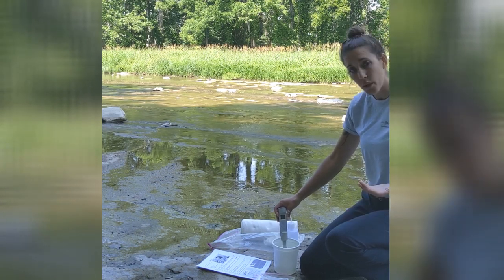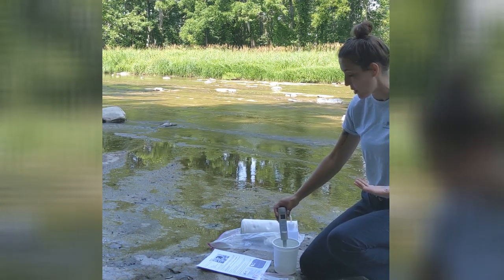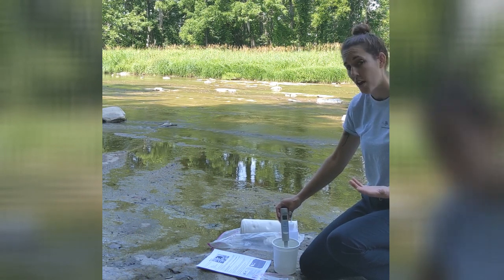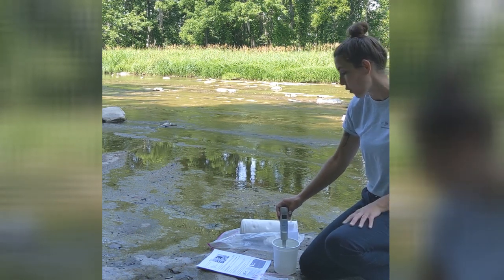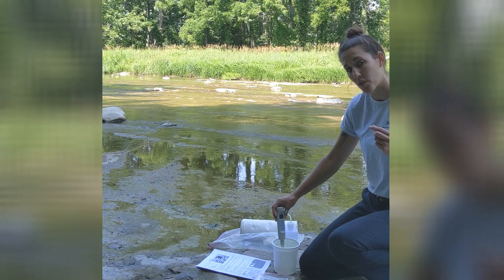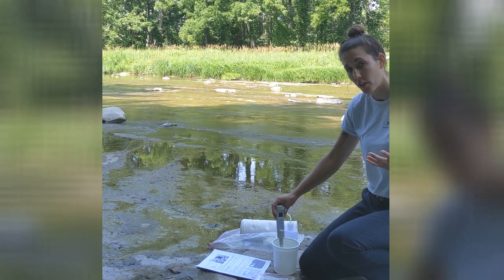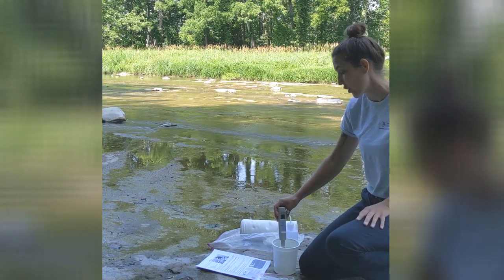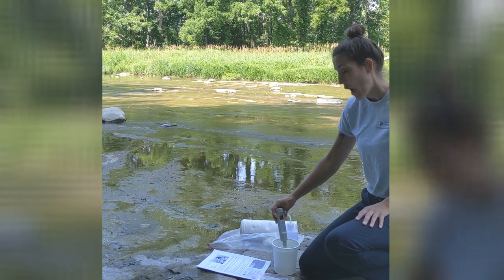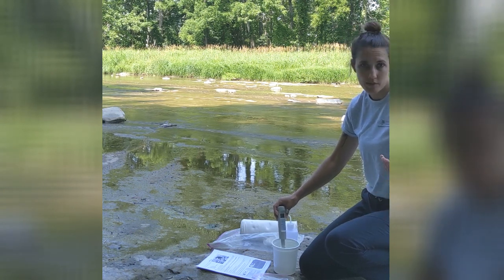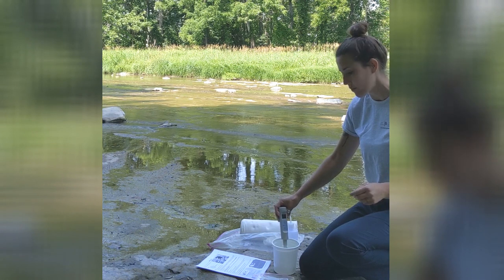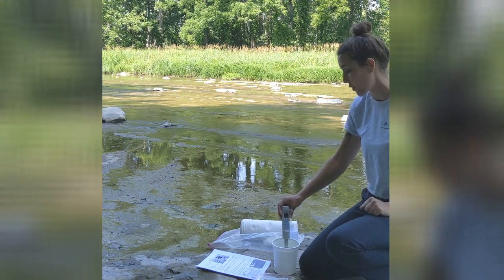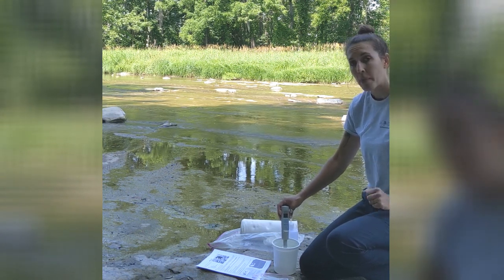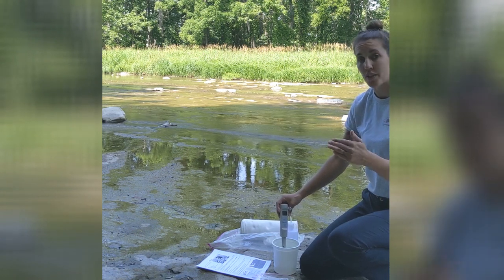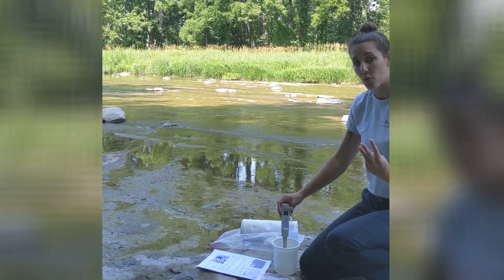Now, you'll notice during this minute that the pH meter might be changing numbers. But after that minute is over, if those numbers are still changing at all, then you're going to wait an additional minute. After that number has stabilized, so it's not moving at all anymore, you're going to record that information on your data sheet, and then you're going to go back to step 1 and repeat this 3 times.